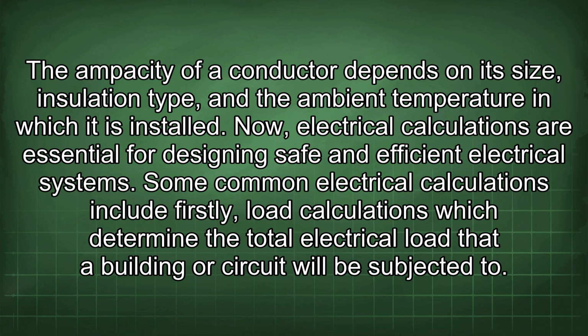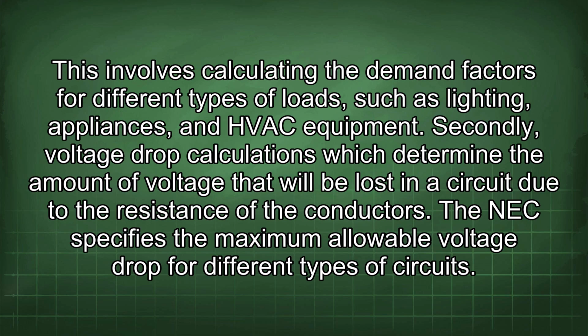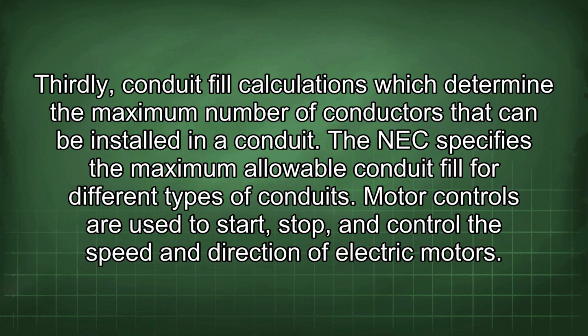Now, electrical calculations are essential for designing safe and efficient electrical systems. Some common electrical calculations include firstly load calculations, which determine the total electrical load that a building or circuit will be subjected to. This involves calculating the demand factors for different types of loads, such as lighting, appliances, and HVAC equipment. Secondly, voltage drop calculations, which determine the amount of voltage that will be lost in a circuit due to the resistance of the conductors. The NEC specifies the maximum allowable voltage drop for different types of circuits. Thirdly, conduit fill calculations, which determine the maximum number of conductors that can be installed in a conduit. The NEC specifies the maximum allowable conduit fill for different types of conduits.